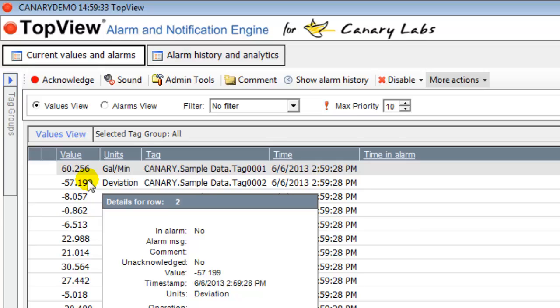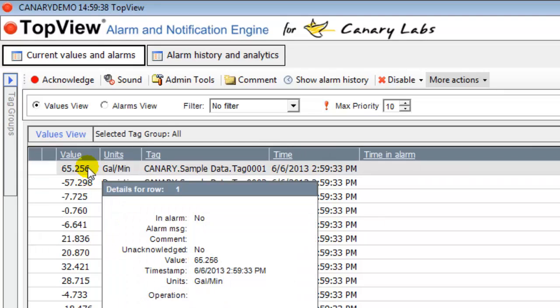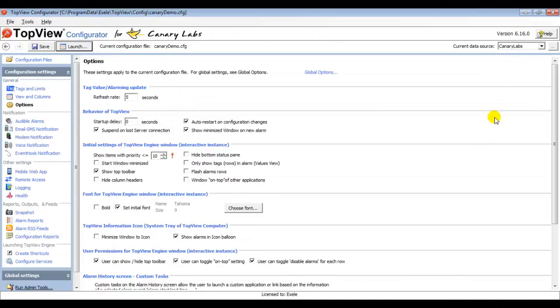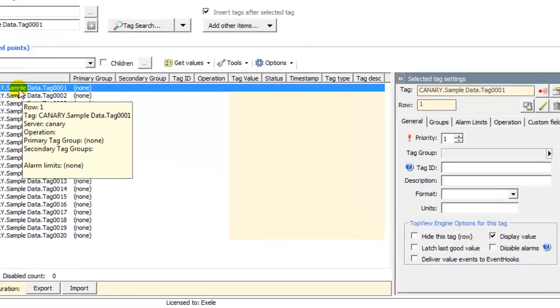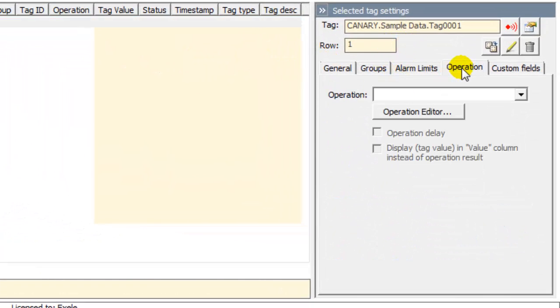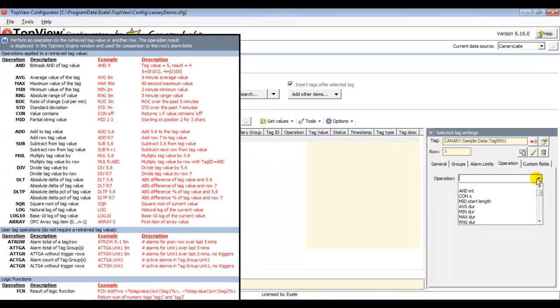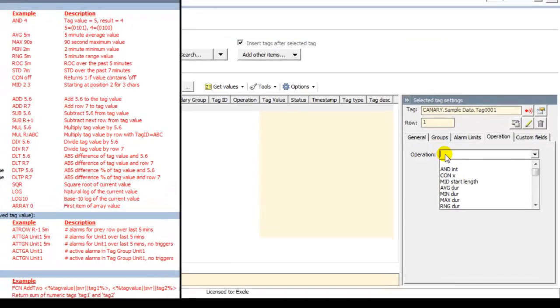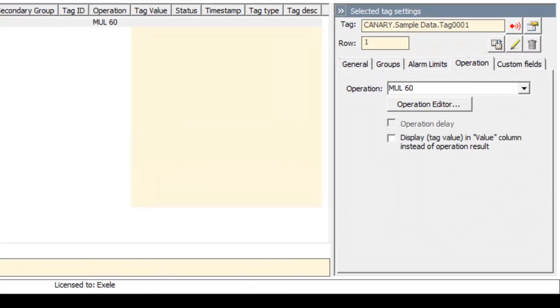I'd like to change the engineering units for one of the listed tags. The first tag is displaying its value as gallons per minute, and I'd like to convert this to gallons per hour. To do this, I return to the Top View Configurator. I need to return to the Tags and Limits screen and select the Flow tag from the list. Next, I click the Operations tab. Top View contains a set of built-in operations that allow you to manipulate the tag value retrieved from the Canary Labs historian. To convert gallons per minute to gallons per hour, I need to multiply the retrieved tag value by 60.